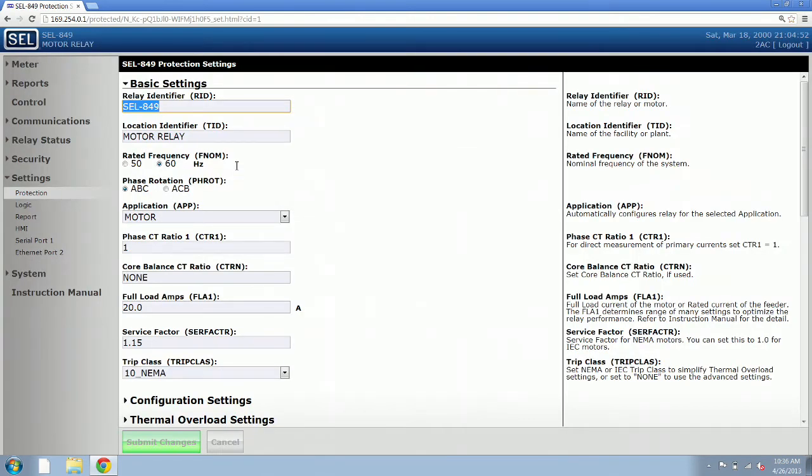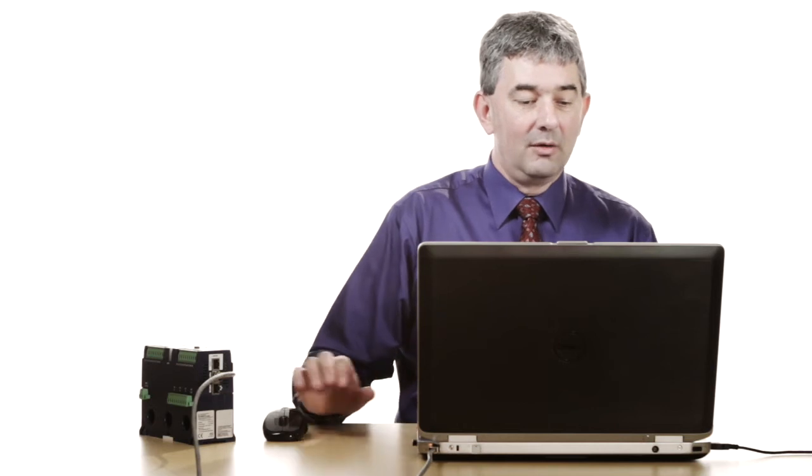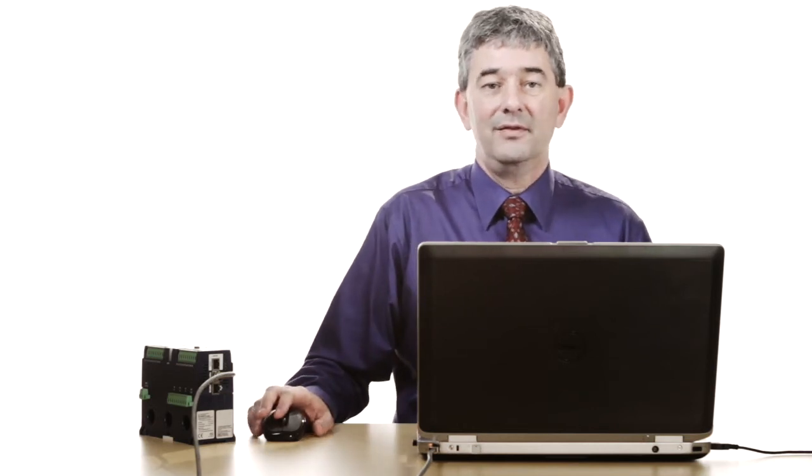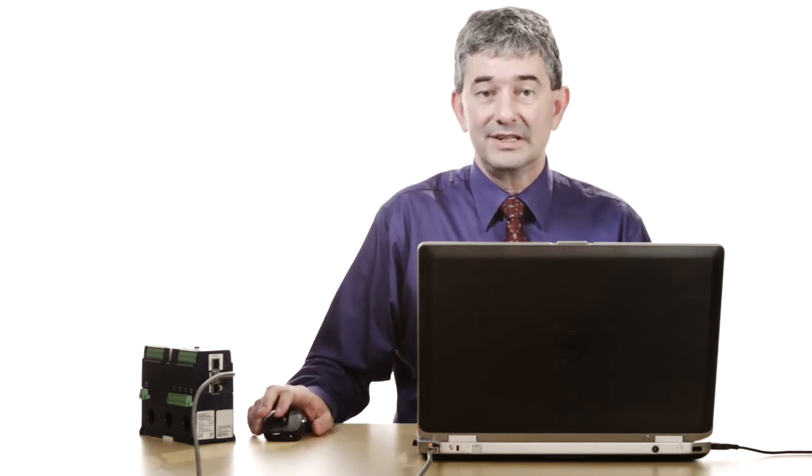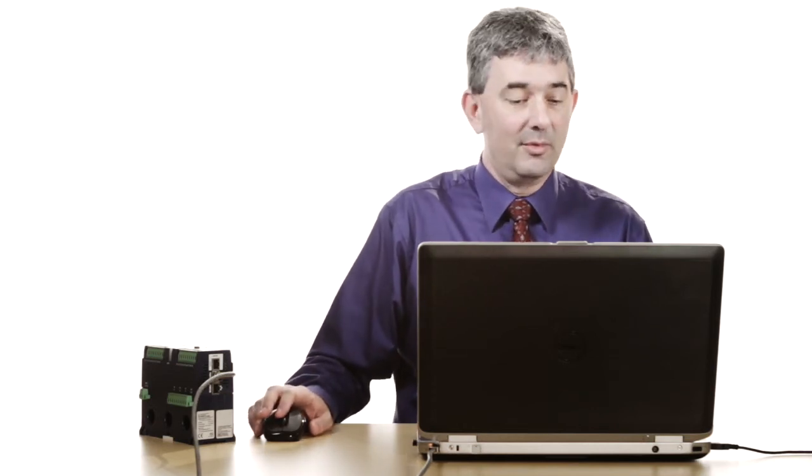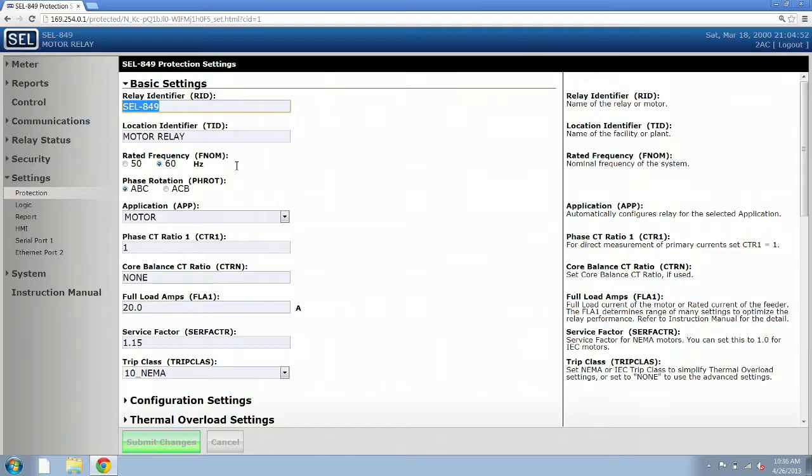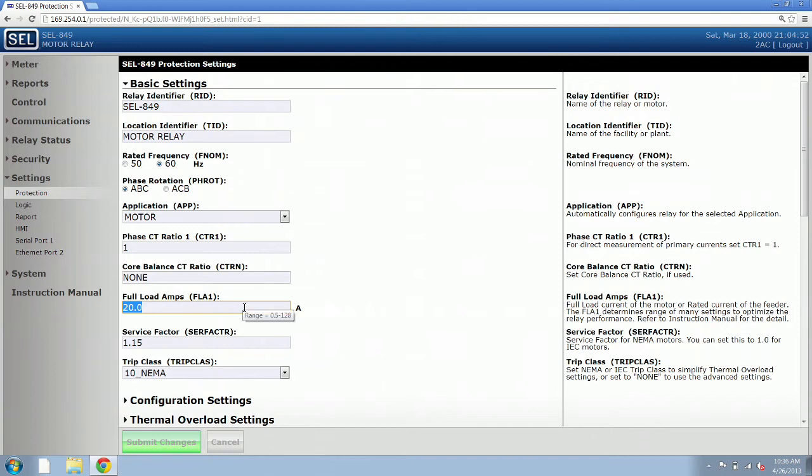We are immediately taken to a basic setup screen. We need three settings to configure this relay for motor overload protection. We get those settings off of the motor itself or the motor overload relay that's already there. In this case, we look at our example motor and we see that it has a full load amperage of 78 amps. Our default is 20, so we just change the 20 to 78.